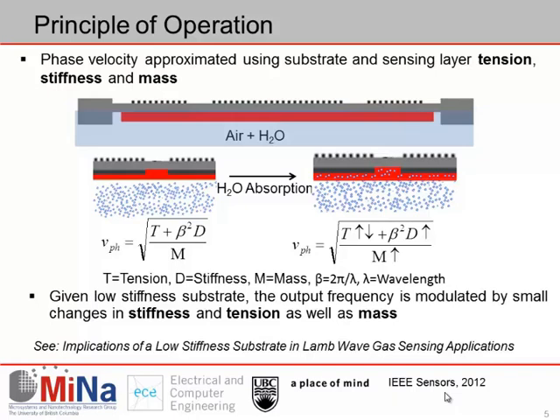In common FPW or SAW sensors, or acoustic sensors like some of those we saw today, the substrate is so stiff that the sensing layer, if it's a polymer, any changes in that sensing layer related to stiffness or tension go undetected. That is, the frequency associated with these changes is completely washed out by any frequency change associated with the stiffness of the piezoelectric material. So given that we have fabricated a low stiffness substrate, the output frequency can be modulated by small changes in stiffness in the sensing layer and changes in tension in the sensing layer as well as mass. For a further theoretical description of this, please see Christoph Sielmann's work in the proceedings, Implications of a Low Stiffness Substrate in Lamb Wave Gas Applications, or check out his presentation yesterday.